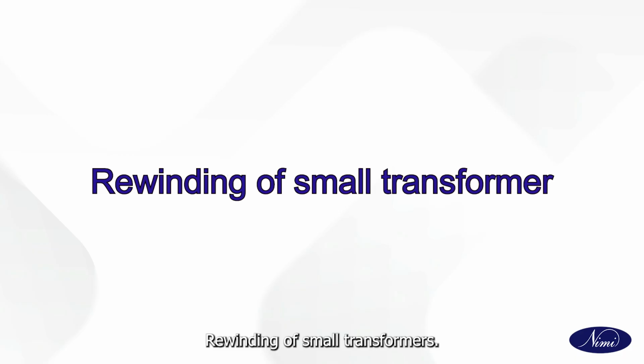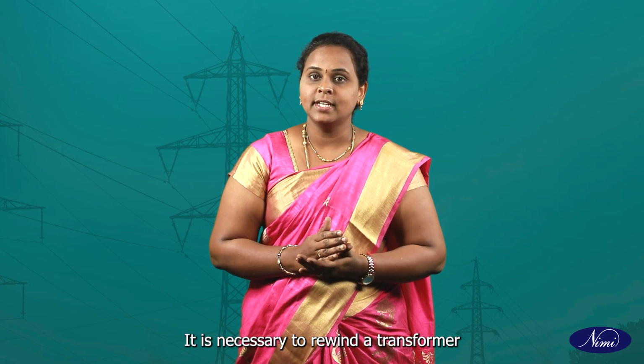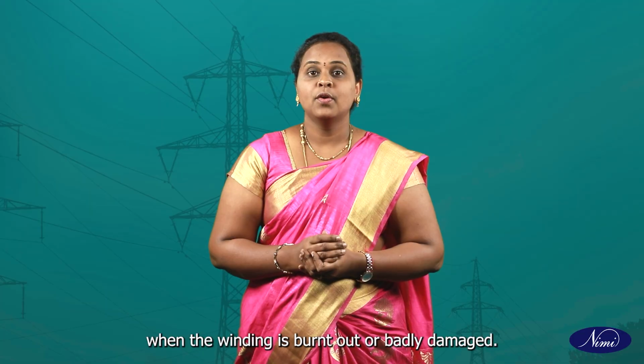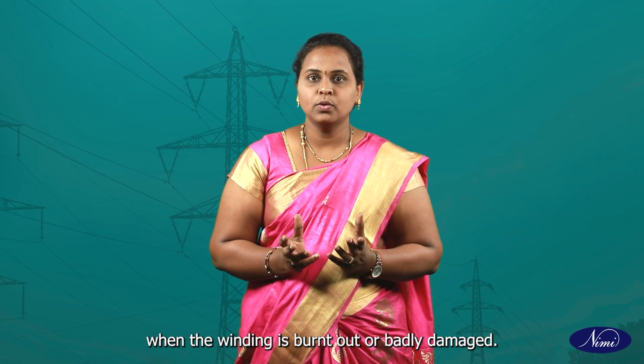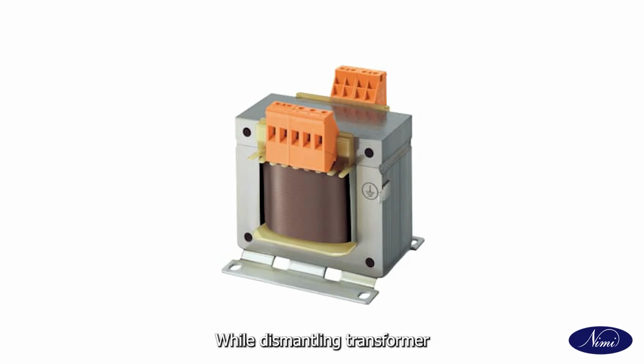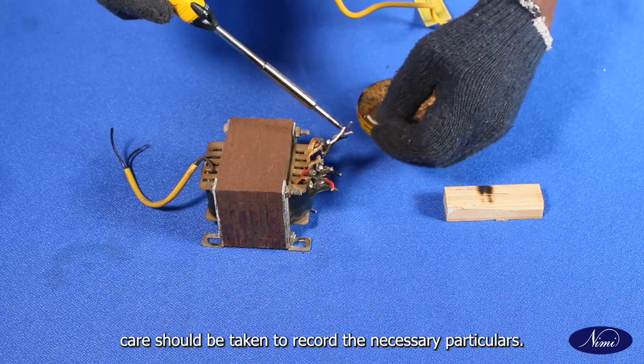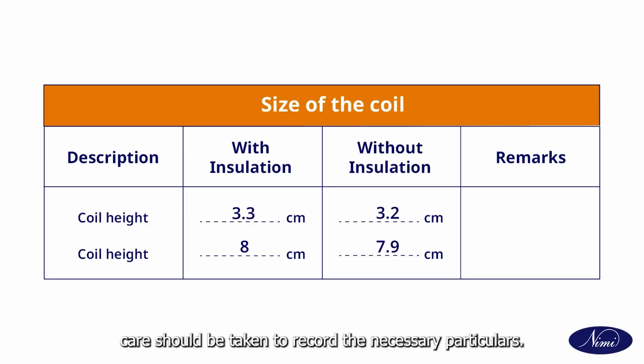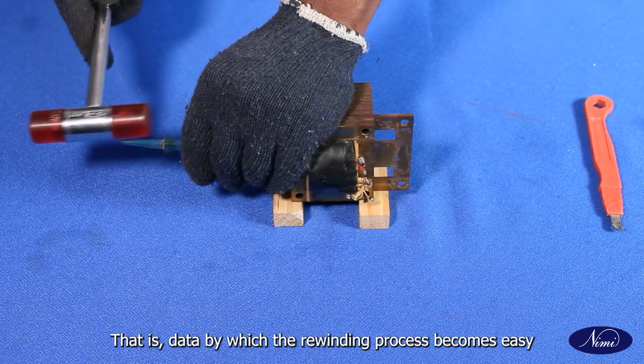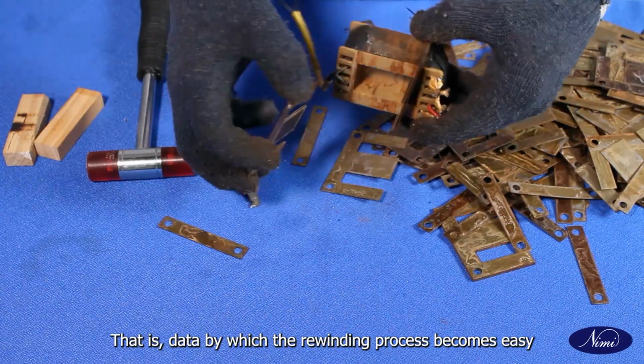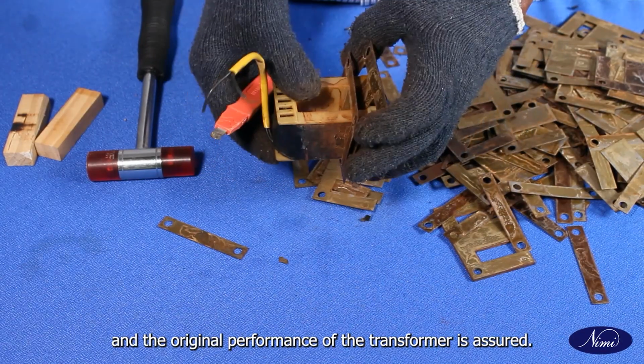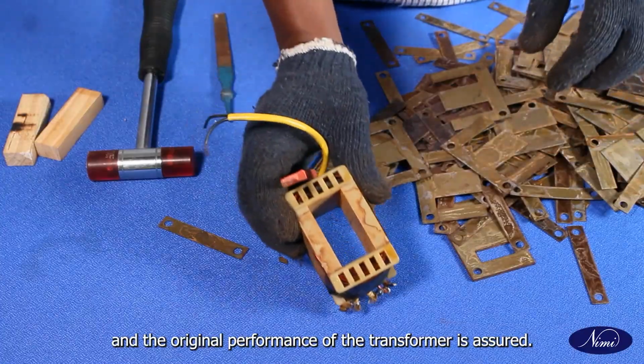Rewinding of small transformers. It is necessary to rewind a transformer when the winding is burnt out or badly damaged. While dismantling the transformer, care should be taken to record the necessary particulars, that is data, by which the rewinding process becomes easy and the original performance of the transformer is assured.